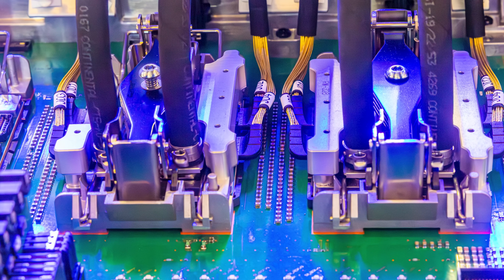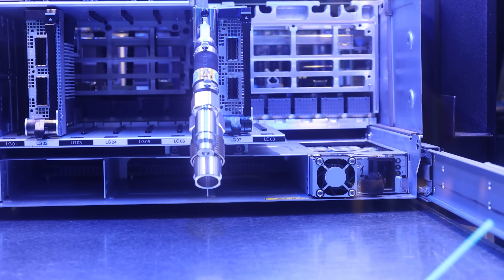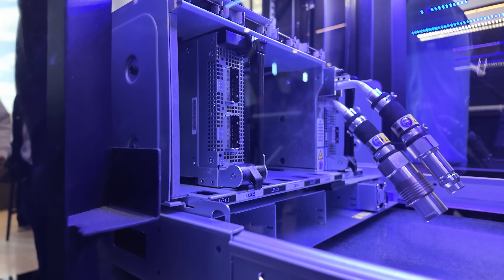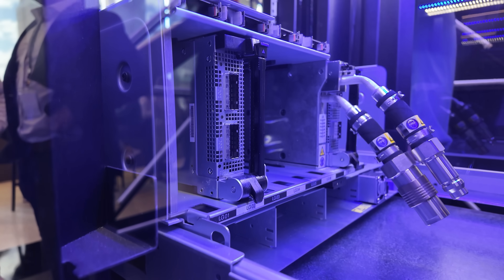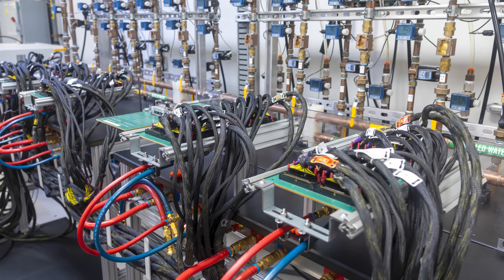That liquid cooling has to dissipate heat somewhere — at the radiator. The systems have a radiator cooling inside, and those systems are designed to run for 10 years with never being serviced. Think about your car: if it were never serviced running 24/7 for 10 years, the radiator would run for almost a million miles. The liquid cooling goes to the rear of the processing drawer, where cards connect to IO trays and the liquid cooling loops. IBM has been doing liquid cooling in mainframes for a long time, so all connectors are tested thoroughly to ensure they disconnect cleanly and maintain reliability — serviced at a maximum of once every 10 years.